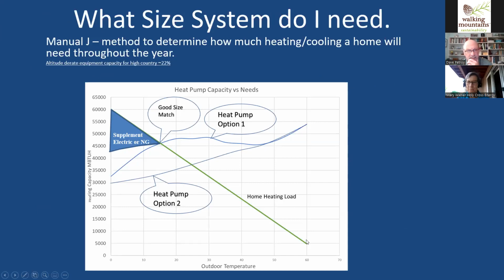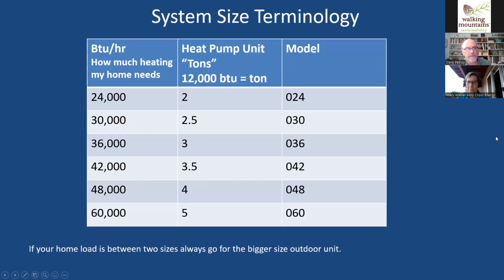The green line is how much heat this house needs. They're going to take a series of heat pumps from the manufacturer - this one wouldn't work, this one wouldn't work - and find which heat pump can match this green line somewhere in the 20 to -5 degree range, so it does 80% or more of your heating. Then when it gets cold, the smart controls kick in: heat pump, heat pump, heat pump, or let me add a little supplemental electric heat, or let me shut the heat pump off and put on a little gas. The intelligence in the system is very good.